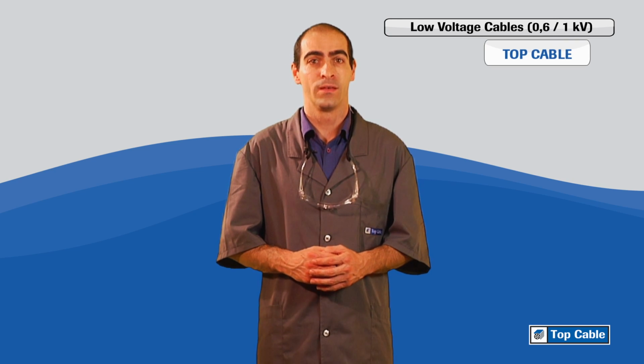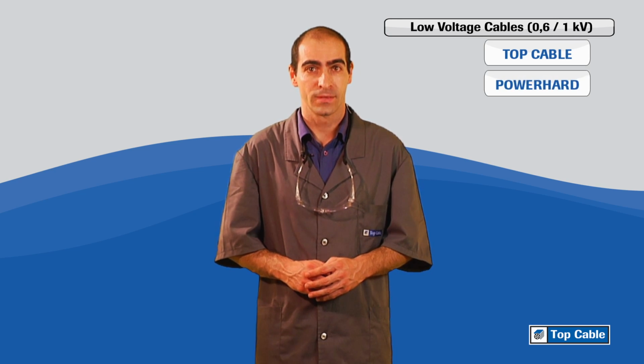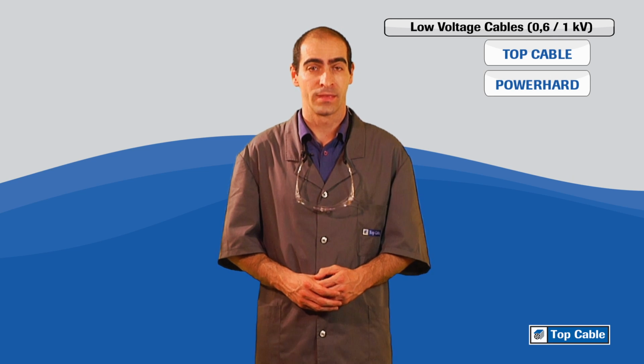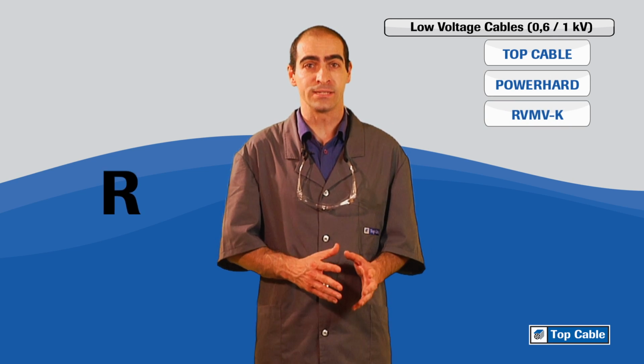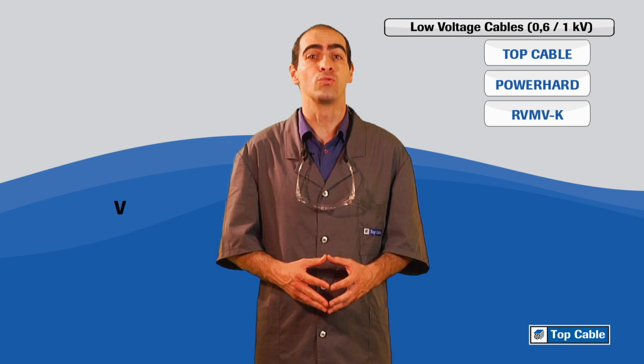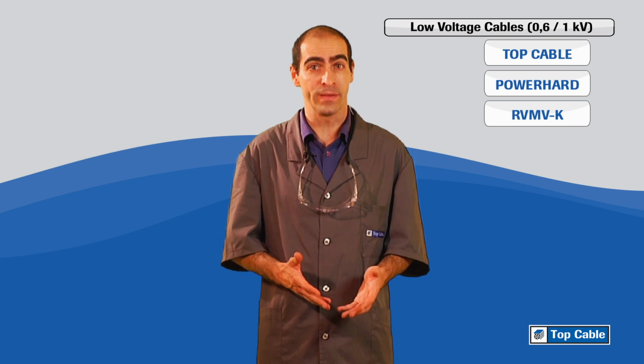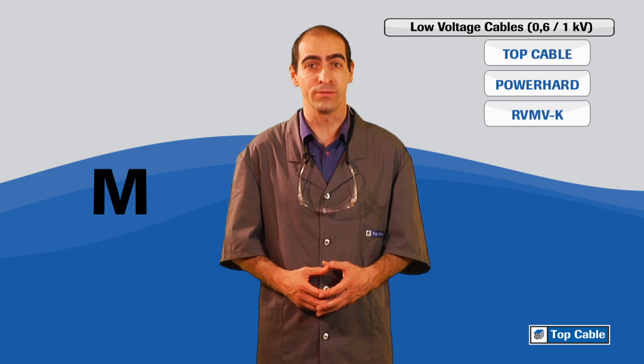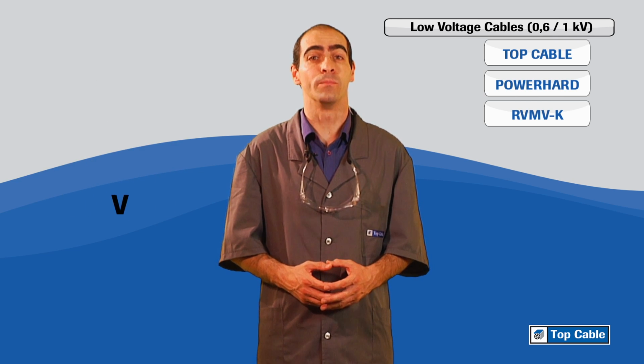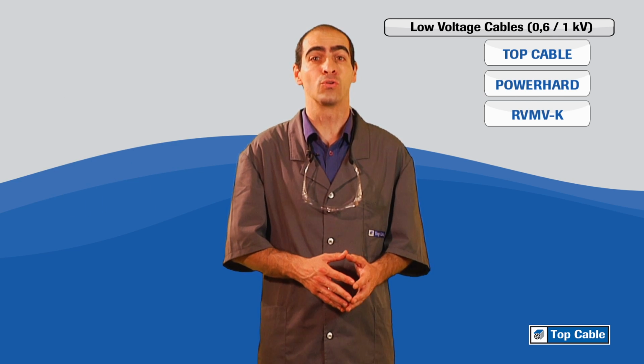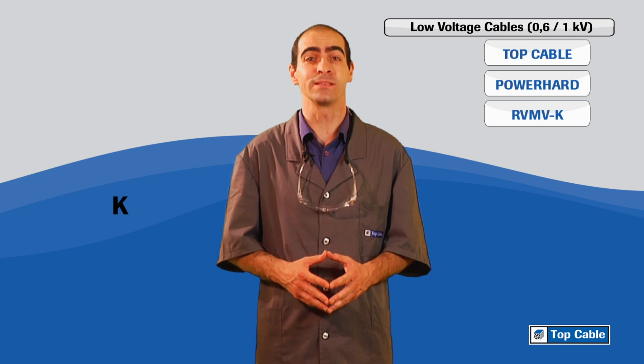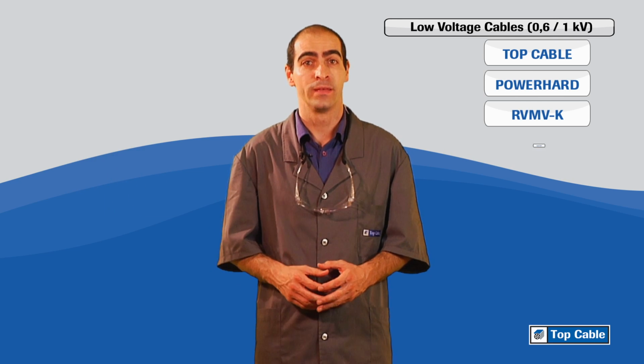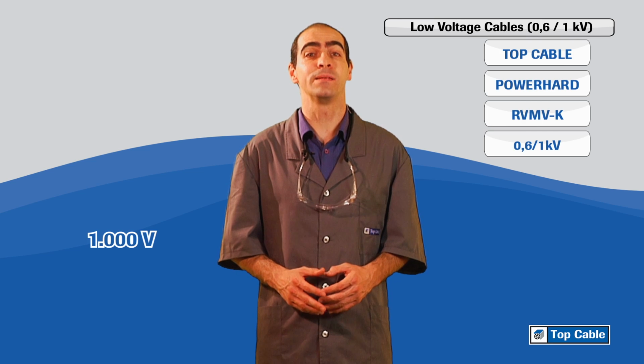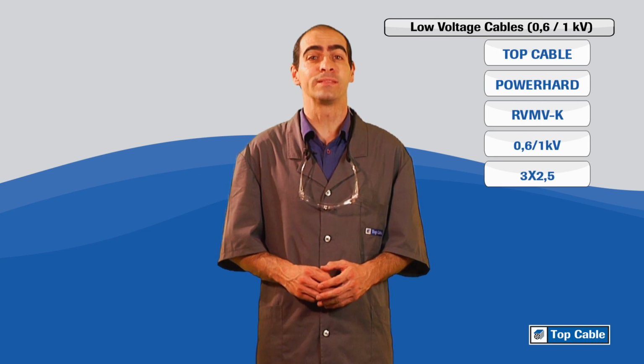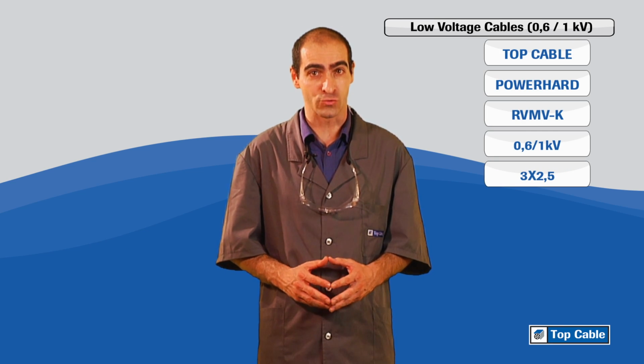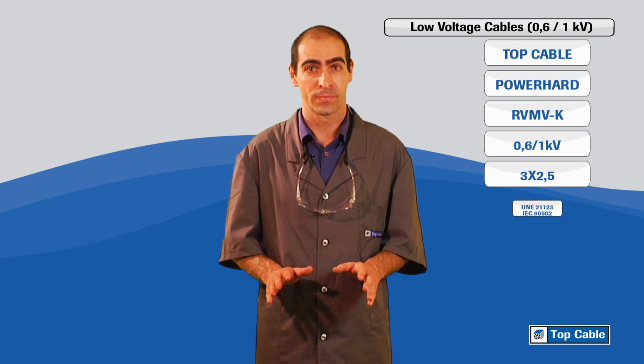Cable manufacturer. Trademark of the manufacturer. Insulated cable with XLPE, R, with a PVC screen, V, steel wire armoring, M, and sheathed with PVC, V, flexible class 5 of IEC 60228 copper conductor for fixed installations, K. The nominal voltage of the cable is 1000 volts. Cable with 3 conductors of 2.5 millimeters squared.